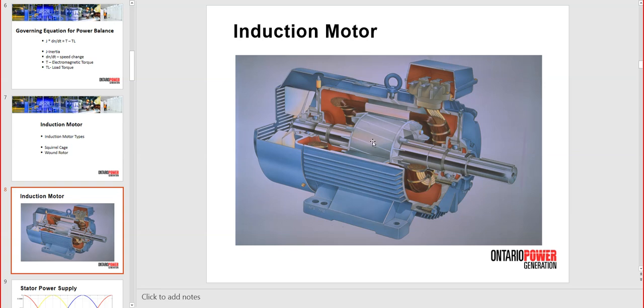A will be on the shelf, B will be on the shelf, as you see it in this picture. A will be high efficiency. What does high efficiency mean? It either has copper bars, not aluminum, or the actual bars are inside the rotor, you don't see them, so the rotor is shiny outside and the bars are inside.